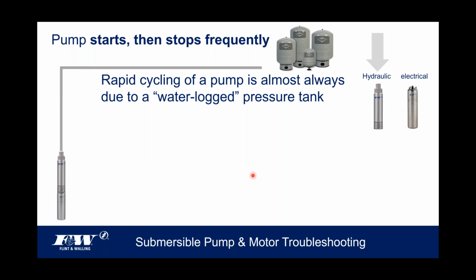So again, back in the day with that old galvanized steel tank, once the water absorbed all that air out of there, this is exactly how that pump would start reacting. On, off, on, off, on, off, every single time water was used. So the service tech would have to go out with his air compressor and pump more air in it, probably a couple, maybe 3 times a year just to keep air in that tank. Well, today, these tanks like we see pictured at the top of your screen are referred to as captive air tanks. And it has gone a long way towards eliminating this problem of waterlogged pressure tanks.